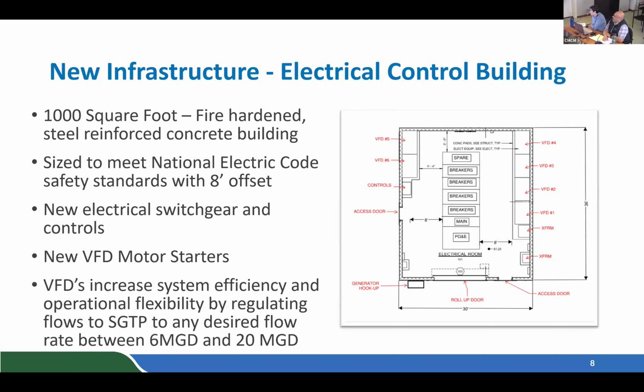We're also including a generator hookup on the outside. So if, let's say PG&E wanted to redo their substation and take away power from that pump station, we'd have the ability to rent a medium voltage generator and run it off a diesel in that type of scenario. Pretty big generator. It's similar to the ones we used at San Geronimo during PSPS. Locomotive engines. Correct. Probably in the scale of 1 to 2 megawatts.